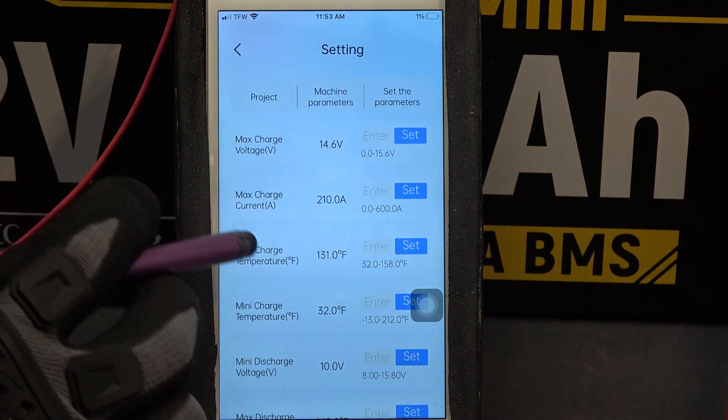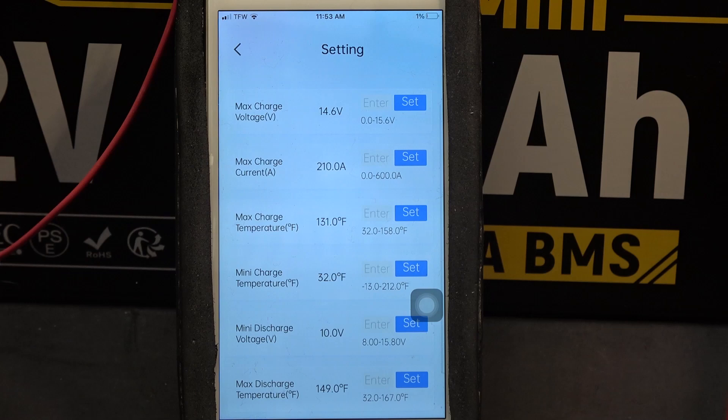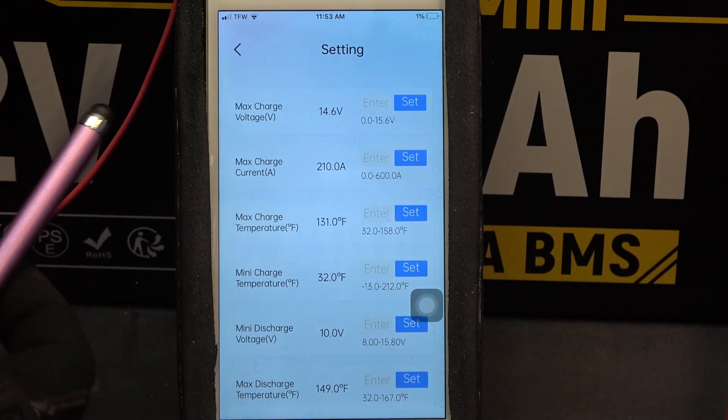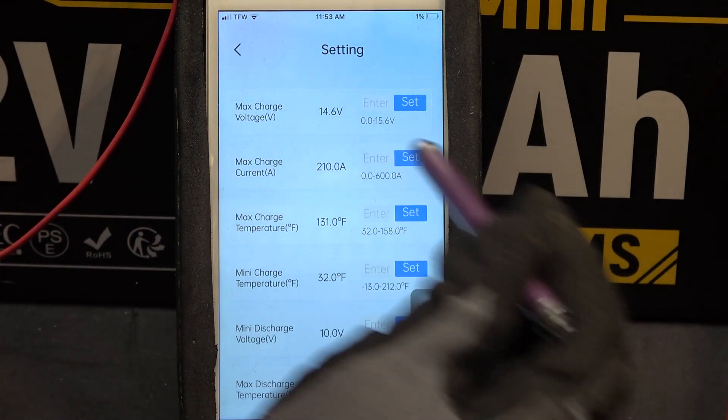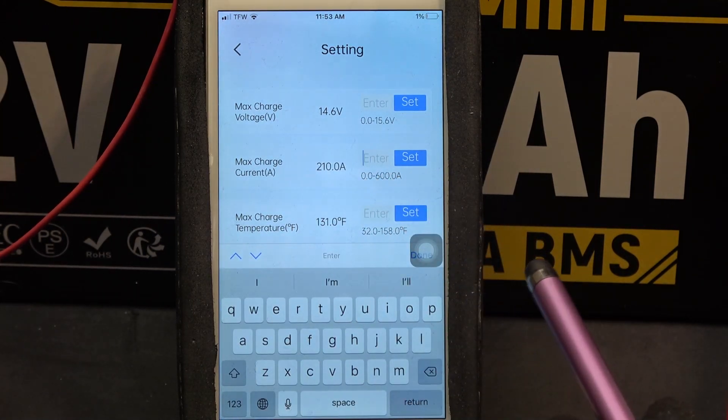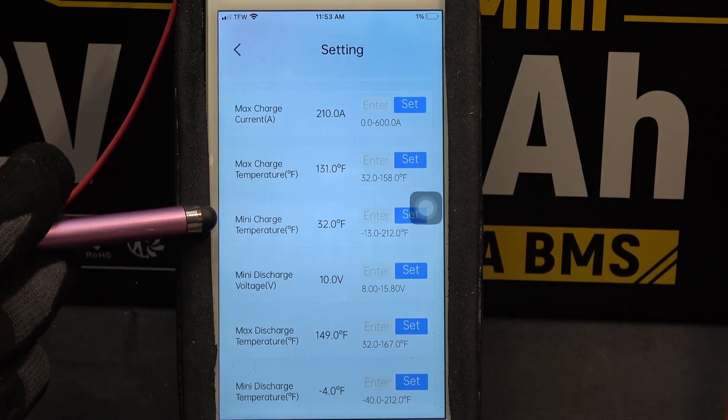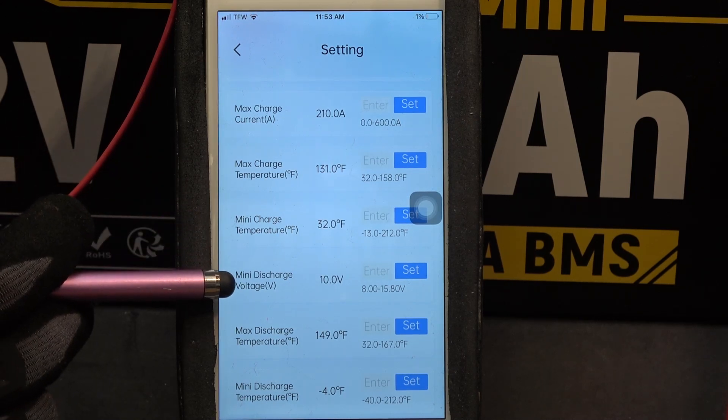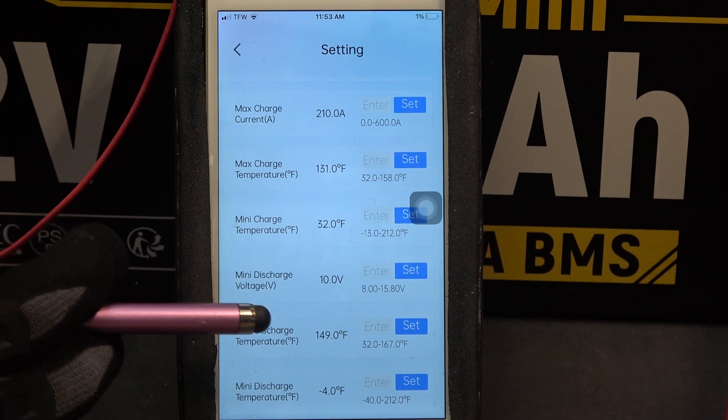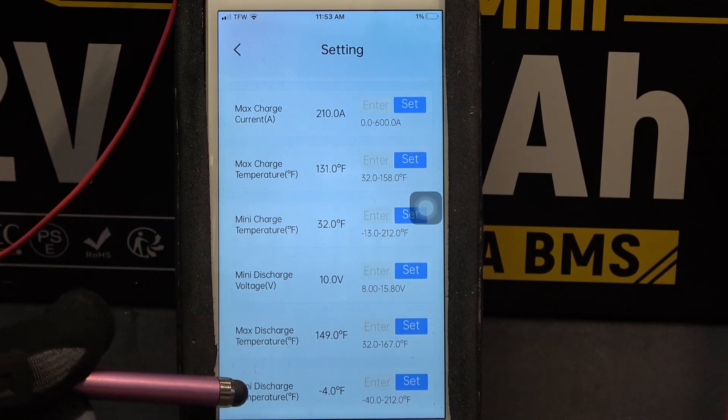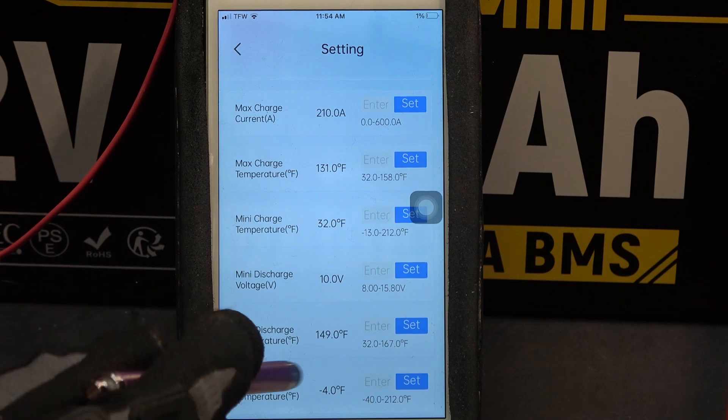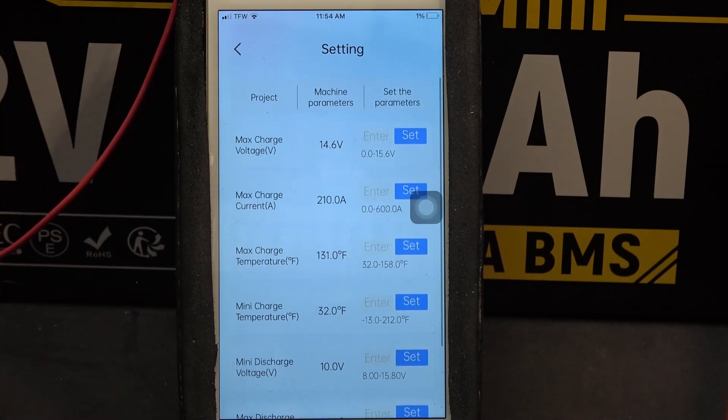You can also change maximum charge current. The default value is 210 amps. You can change this value from 0 to 600 amps. You can change maximum charge temperature, minimum charge temperature, minimum discharge voltage, maximum discharge temperature, and minimum discharge temperature. And that is all for the setting.